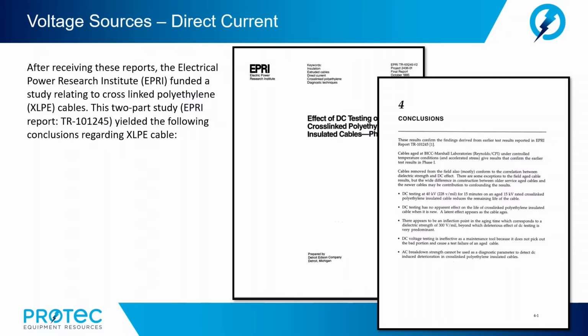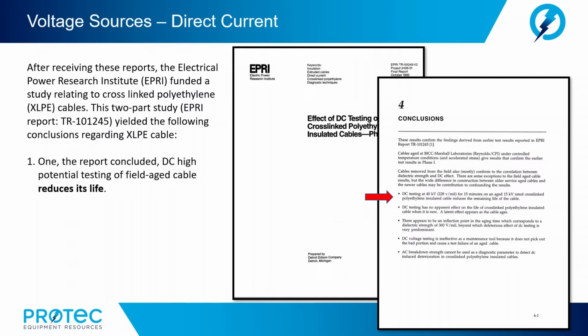Now, after receiving these reports, the Electric Power Research Institute, or EPRI, funded a study relating to cross-linked polyethylene, XLPE, cables. The study, which is EPRI Report TR-101245, yielded the following conclusions regarding XLPE cable. First, the report concluded DC high potential testing of field-aged cable reduces its life. Secondly, DC high potential testing is ineffective as a maintenance tool. And finally, the report concluded DC high potential testing before energizing new medium voltage cable does not cause any reduction in service life.